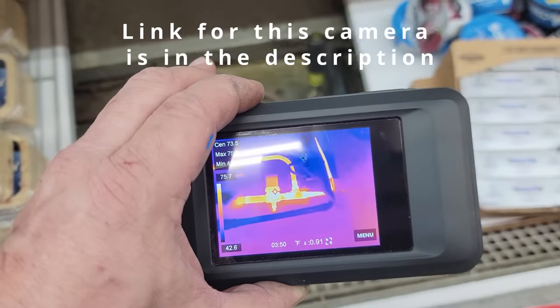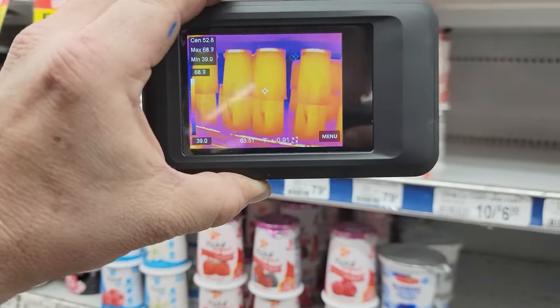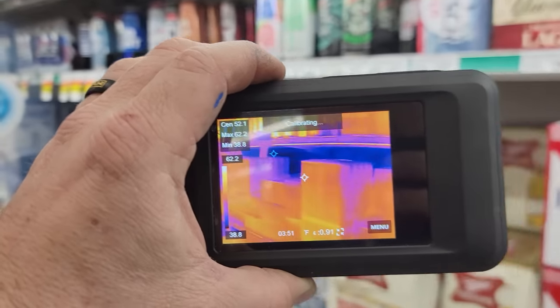We are feeding through there, but unfortunately our solenoid still does not have any power. We have at least dropped some of our case temperature. Some places are definitely cooler than others. This product in the back is all warm now, but we're definitely getting cold all the way back to here. This thermal imager is freaking amazing compared to what I had before — day and night difference. You can see such definition; you can tell that one's colder than the other, plain as day.